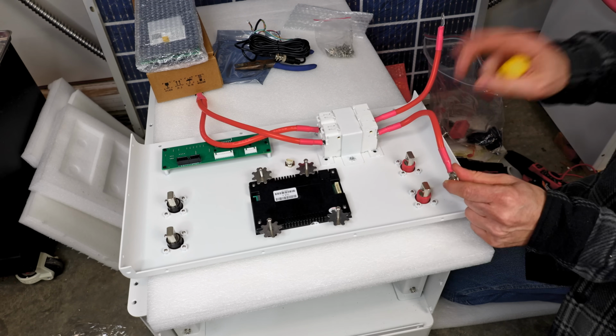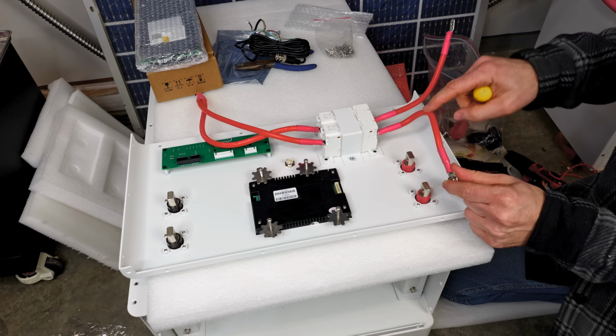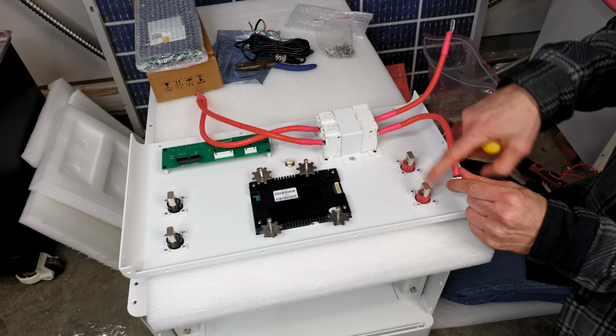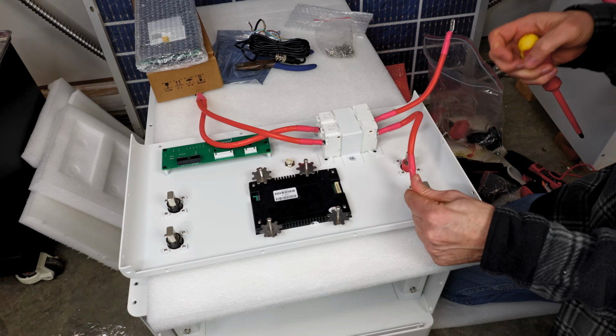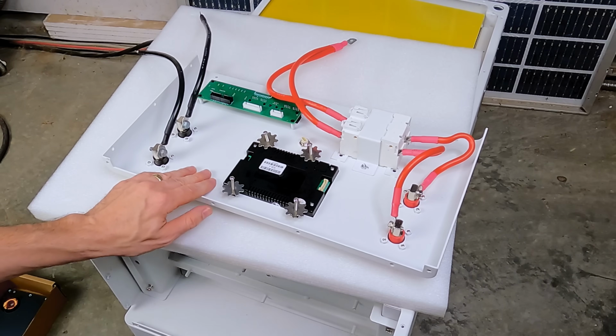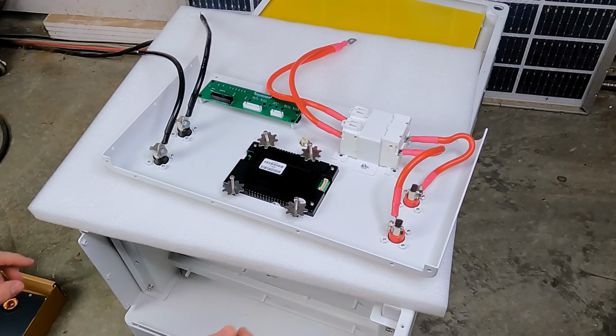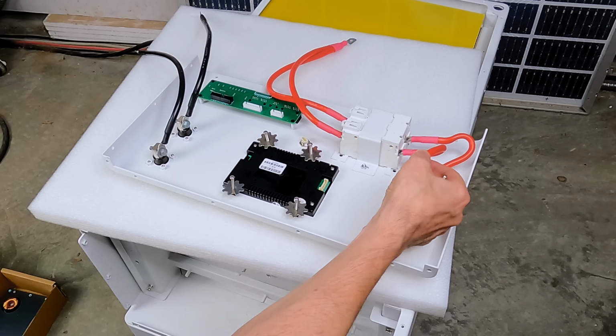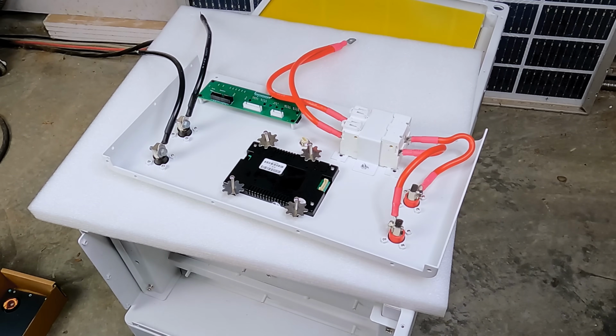That's a problem. To correct it, these need to each be 4-gauge instead of 6-gauge, and I need a bus bar across these two. I've talked to the supplier about this kit and let them know that this 6-gauge wire is insufficient.